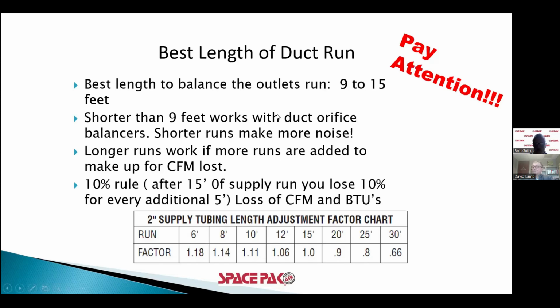Shorter than 9 feet works with a duct orifice, we call it a balancer. But the shorter they are, the louder they are as well, so keep that in mind. Longer runs work if more runs are added to make up for lost CFM. We've got the 10% rule: after 15 feet of supply run, you lose 10% for every additional 5 feet or part thereof, in loss of CFM and BTUs.